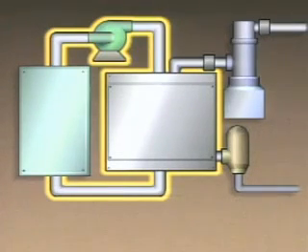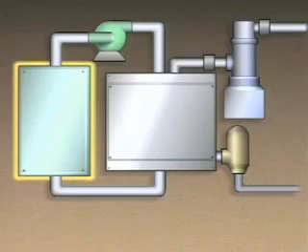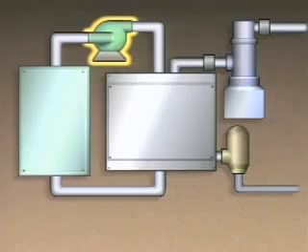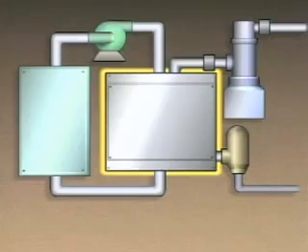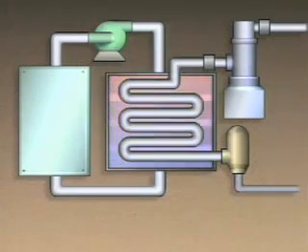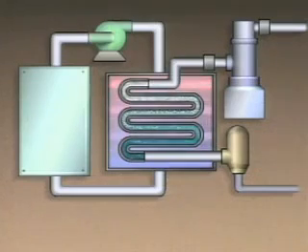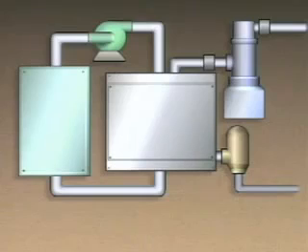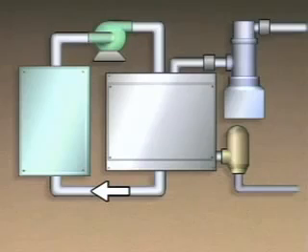The system in our example uses a brine solution. The brine flows through the process equipment where it absorbs heat and cools the equipment. A pump creates flow through the brine cooling system, and the brine is then pumped to a heat exchanger. The heat exchanger in the brine cooling system is the evaporator in the refrigeration system. In the evaporator, the brine acts as the heat source and its heat is absorbed by the refrigerant. As the refrigerant flows through the evaporator, it changes to a vapor and flows on through the rest of the refrigeration system, while the cooled brine is directed back to the process equipment.